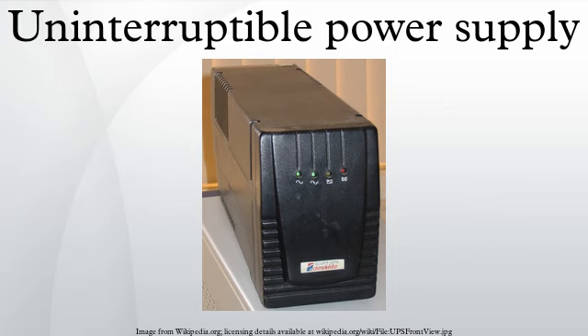In low voltage conditions the UPS will use more current than normal, so it may need a higher current circuit than a normal device. For example, to power a 1000 W device at 120 V, the UPS will draw 8.33 A. If a brownout occurs and the voltage drops to 100 V, the UPS will draw 10 A to compensate. This also works in reverse, so that in an overvoltage condition, the UPS will need less current.